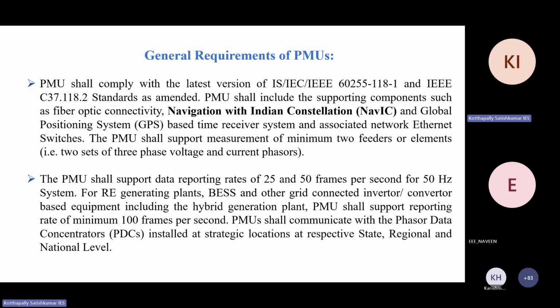As many of you know, it's the Indian GPS, NavIC, navigation with Indian constellation. So recently, last year, NRLDC piloted this. Instead of GPS, they used NavIC signals for synchronization. So in the near future, in the general requirements of PMU, we have also mentioned this. The future PMUs, present PMUs, and upcoming manufacturers of PMUs are mandated with this condition: even if the GPS signal is lost, they should immediately lock with the NavIC signal to measure the real-time power system. So there is no problem even if GPS is withdrawn on the power system.